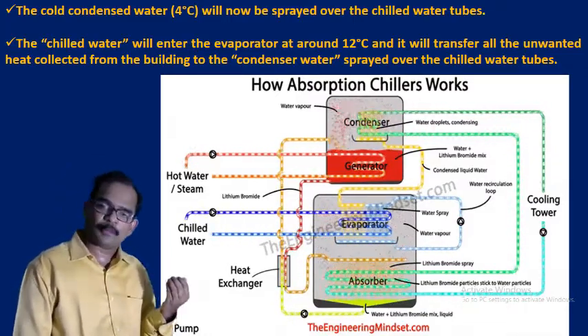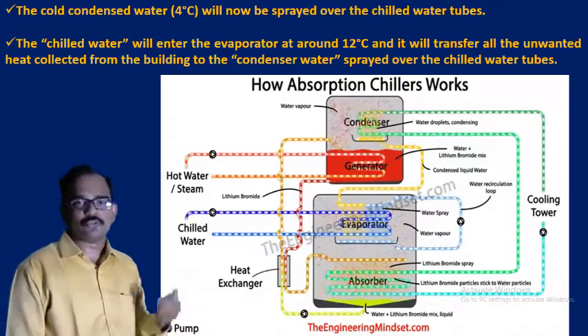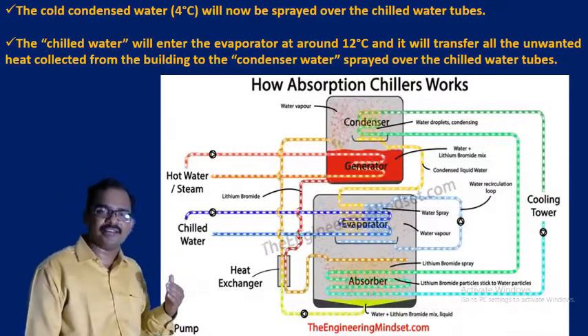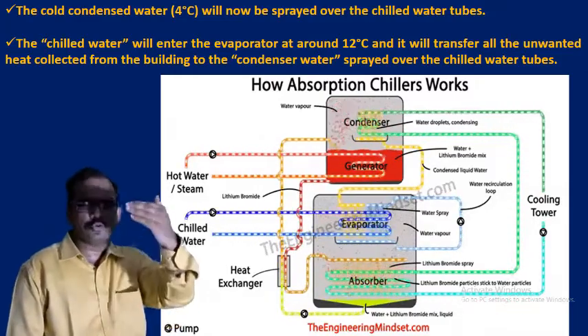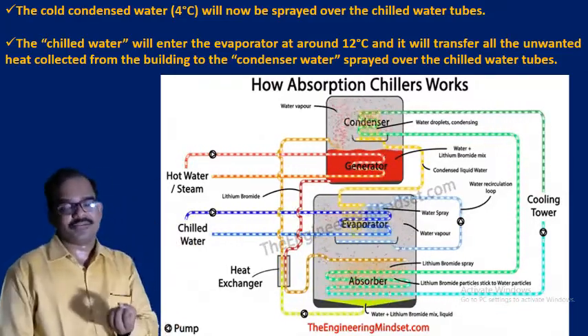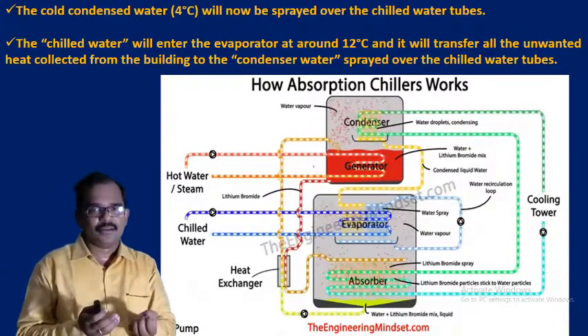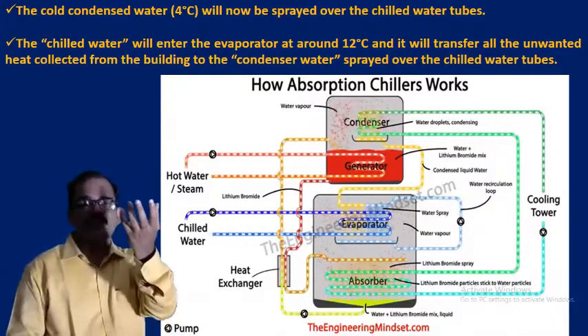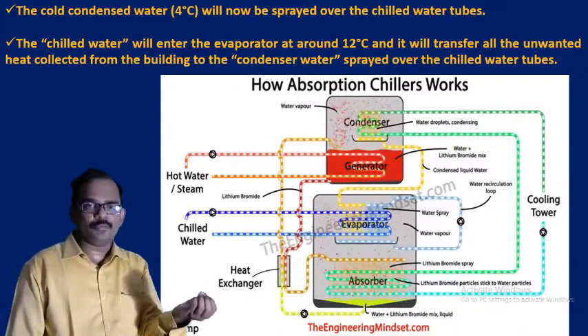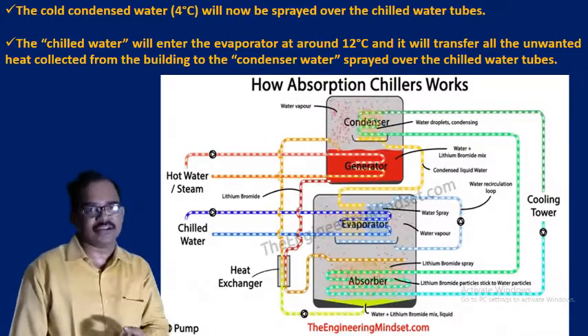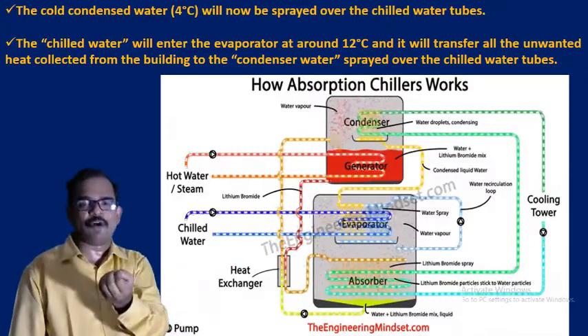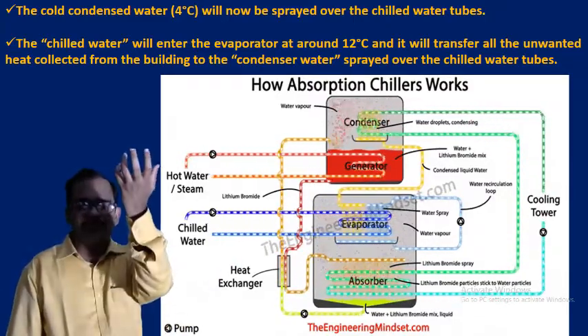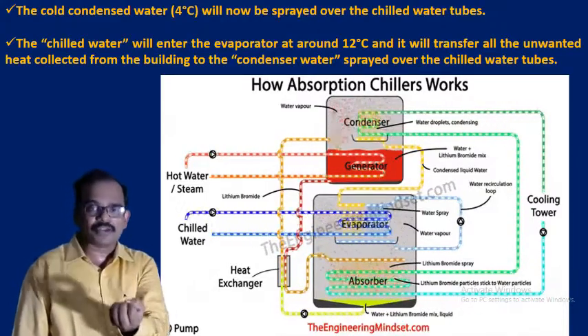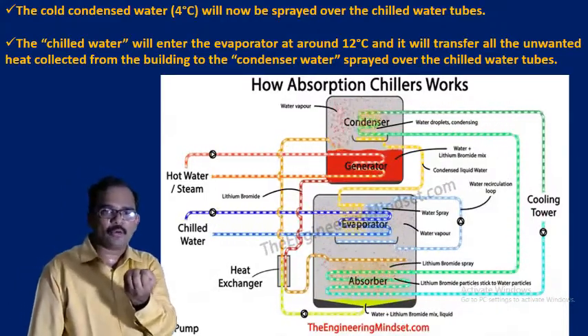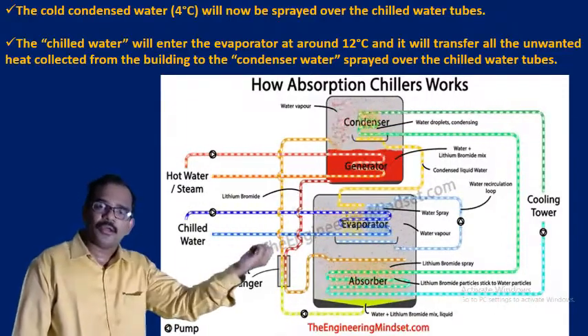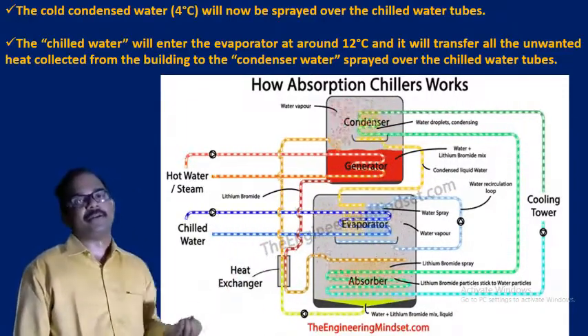So normally heat will flow from high temperature to low temperature. So the heat which is available in the 12 degrees centigrade chilled water will now move to the condenser water. That is, it will lose its heat by 4 degrees centigrade, because the condensed water is at 4 degrees centigrade. That is, the chilled water which is entering the evaporator at 12 degrees centigrade, after being sprayed by the condenser water, will reduce its temperature to around 8 degrees centigrade while it is moving out of the evaporator.